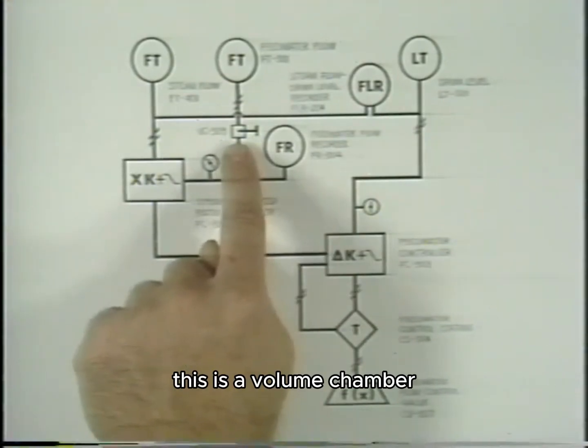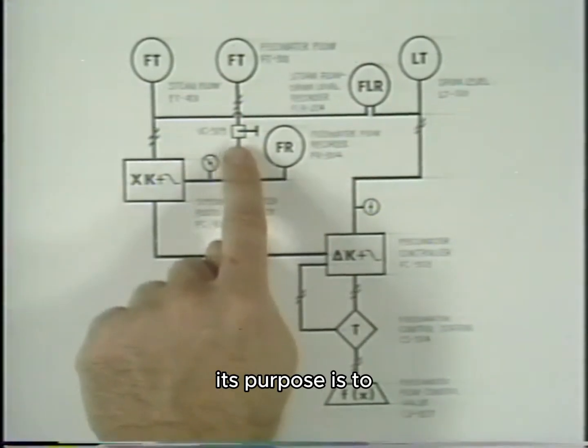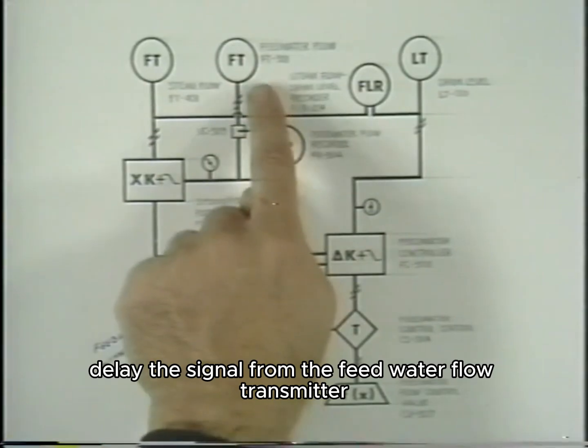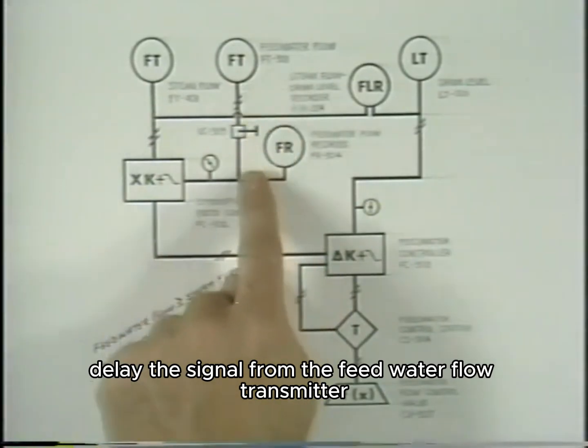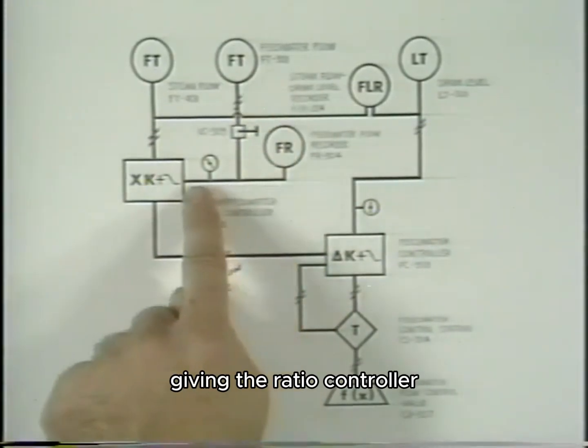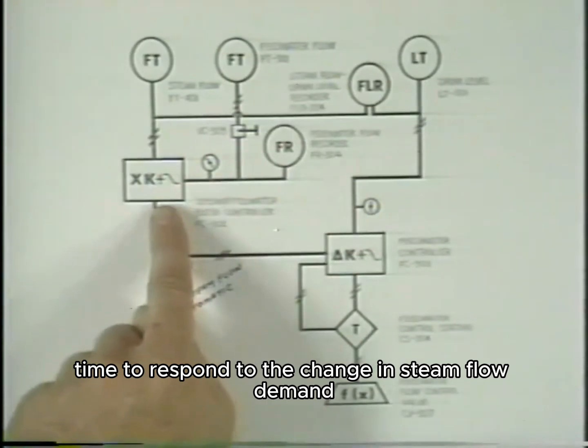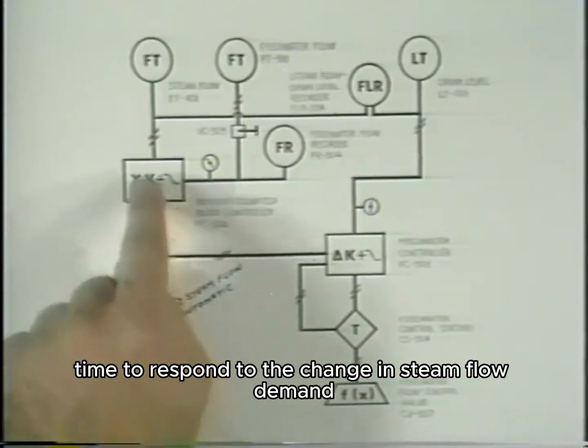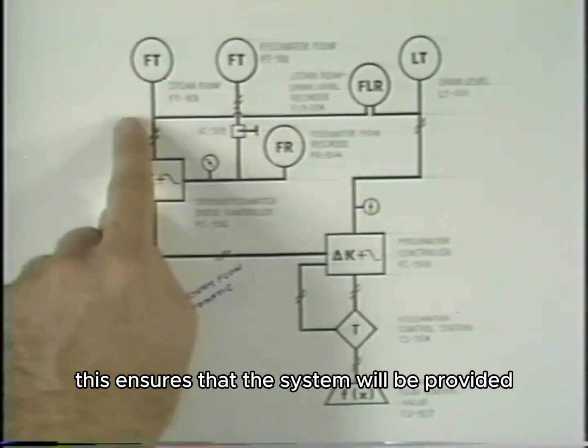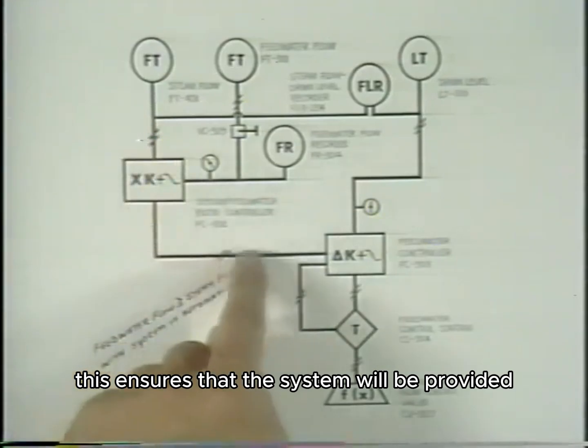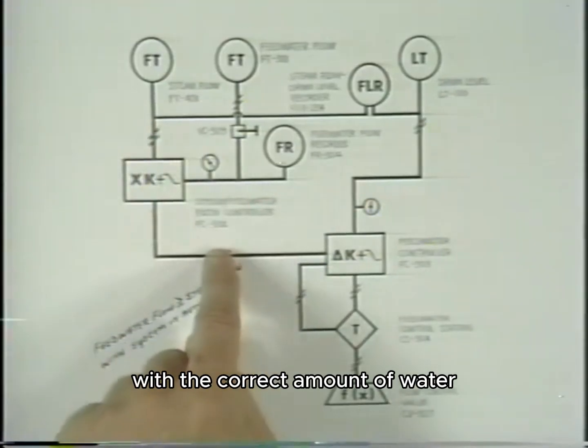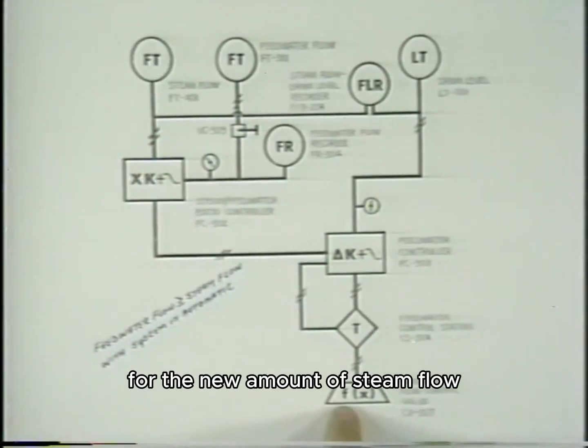This is a volume chamber. Its purpose is to delay the signal from the feed water flow transmitter, giving the ratio controller time to respond to the change in steam flow demand. This ensures that the system will be provided with the correct amount of water for the new amount of steam flow.